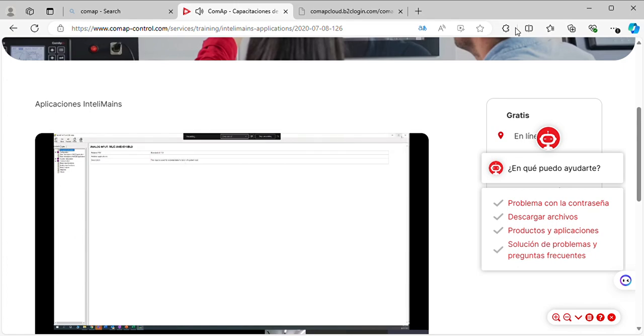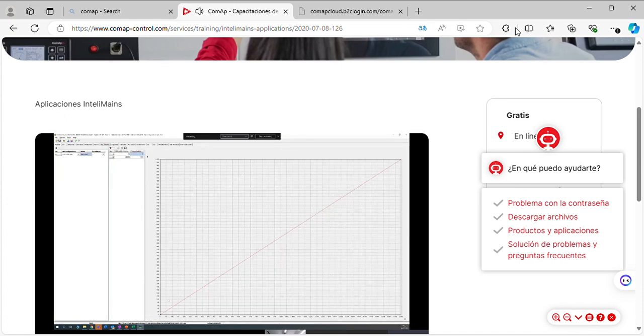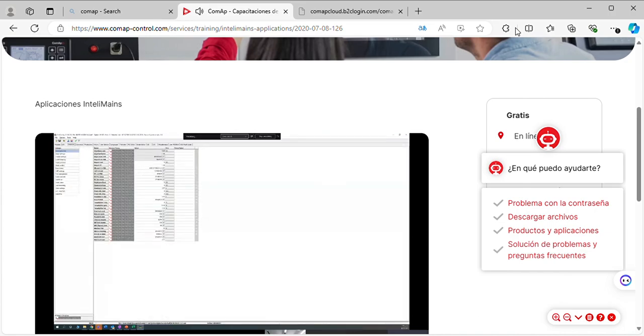So once you have done that, and once you rotate that potentiometer, it would vary from 0 to 2000 ohm. And at say 1000 ohm, it will give you near about 500 kilowatt of base load. So you can vary this value. Just by selecting your set point and choosing the kind of operation you want, whether a set point based base load or external base load control, this is how the base load operation works.